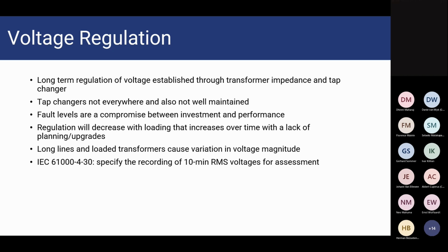So regulation will decrease with loading that increases over time and will also be impacted by a lack of planning and upgrades. Long lines and loaded transformers cause a variation in voltage magnitude. All right, so that's just the introduction on what can impact your voltage regulation. The IEC 61000-4-30 specifies the recording of 10-minute RMS voltages for assessment. So if you need more information on how voltage magnitude and RMS voltages are calculated and measured, that is defined in the IEC 61000-4-30.